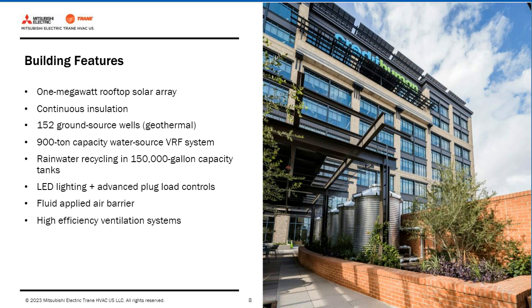Additionally, I mentioned high efficiency ERV and ventilation systems. There is also really advanced LED lighting and advanced plug load controls. So the control system, I think Matt might talk about, runs under the flooring so that they've got a grid which can monitor the zones of electrical use for each of the zones on each of the floors, which allows them to optimize the energy use of those systems as well.